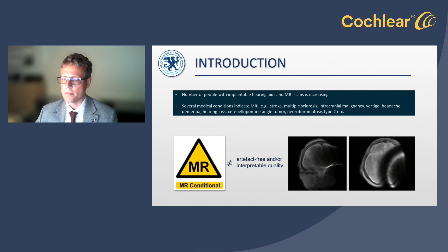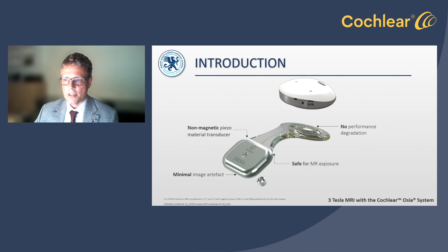The majority of hearing aids and hearing implants is MRI conditional. It means that the MRI examination can be performed under certain conditions, but this not necessarily means that the implant will not limit the diagnostic value of the examination field, especially the head. The Osia system, the implanted part, the OSI 300, is like many recent implants, MRI conditional. We can perform MRI examination. This implant has a removable magnet, which means that we can perform imaging examinations, MRIs, without much limitation.